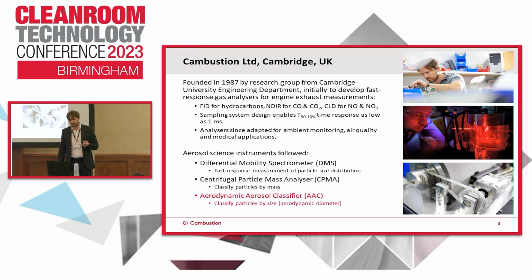But the key thing was the sampling system was designed to preserve very high temporal resolution. So we have time responses down to about 1 millisecond. So wherever there's a need to measure rapidly changing concentrations, or you're anticipating having to measure short-lived spikes in emissions, our instruments are well set up for that. And then since then, the analyzer has been adapted for ambient monitoring, air quality, and medical applications.